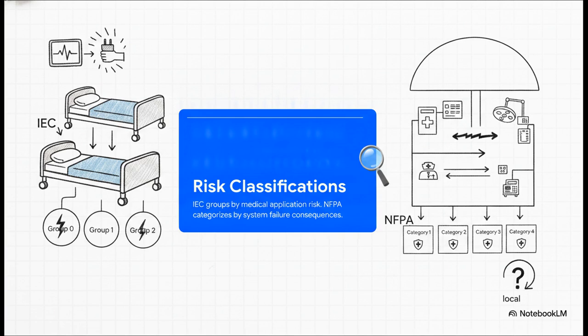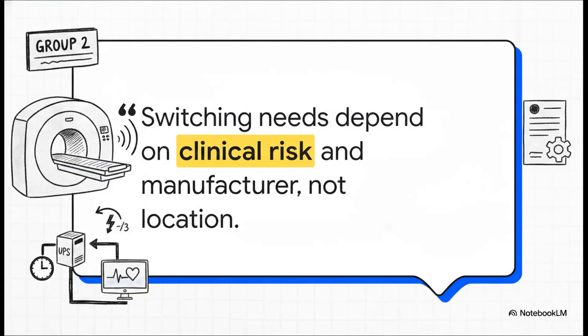The IEC standard categorizes spaces into groups 0, 1, and 2 based on the medical application, basically asking, are applied parts touching the patient, and will a power loss threaten their life? Meanwhile, the NFPA standard in the US focuses on categories 1 through 4, which define the broader risks to both patients and staff if the system fails. You absolutely must know which standard your region is actually enforcing. This guideline from the UK's NHS illustrates this perfectly.